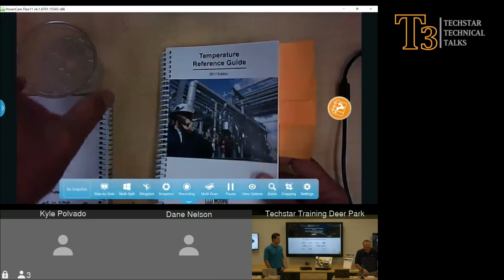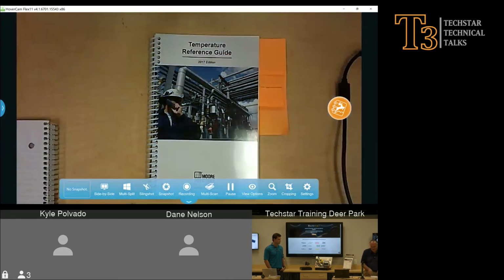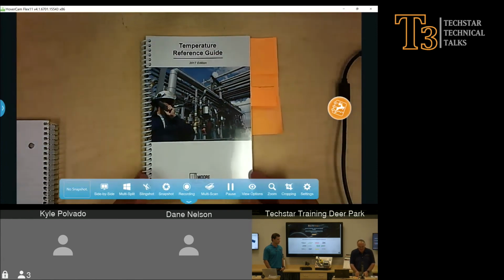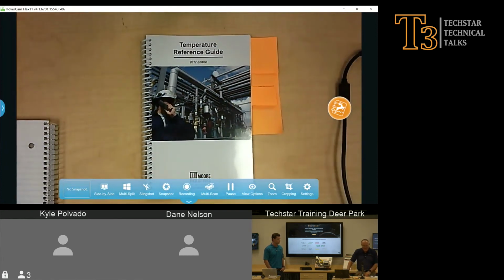That was kind of fast and furious. So let me talk about this temperature guide. This is something you should have on the back of your shelf. It's compact, and I like it because over the last 20 years, no one really messes with cold junction reference or likes to look up the resistance chart, because transmitters are so smart. They're 20-bit ADCs. They have 1 part in a million resolution. They have isolation, which we can talk about, and the curves are built in. But typically, if you get the 0 right, you're going to be in pretty good shape.